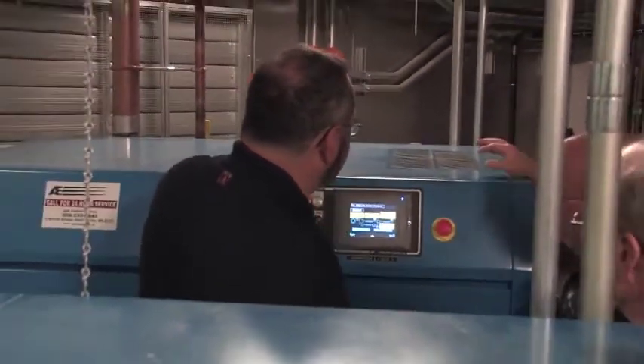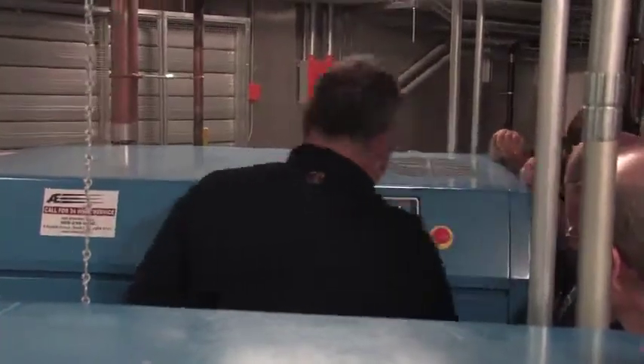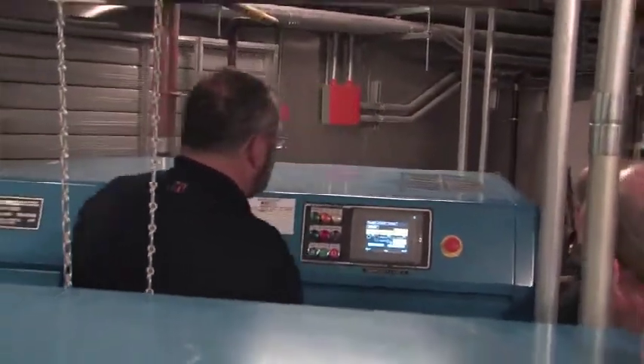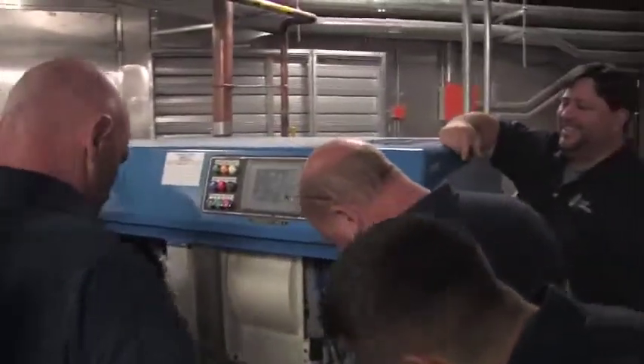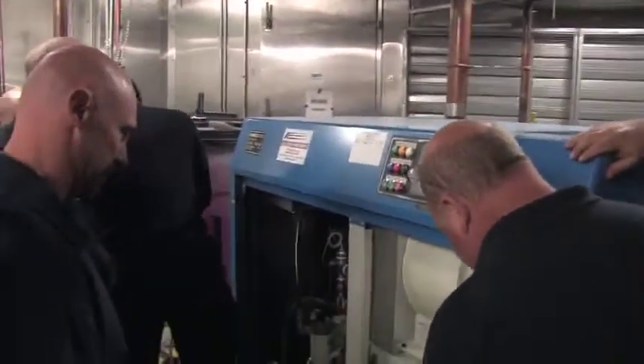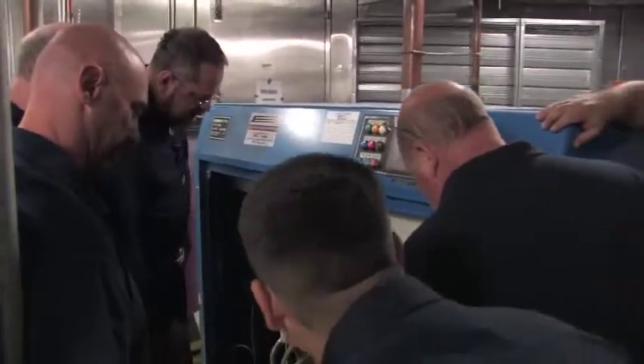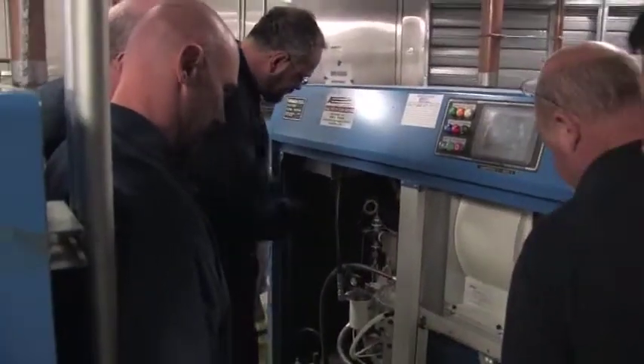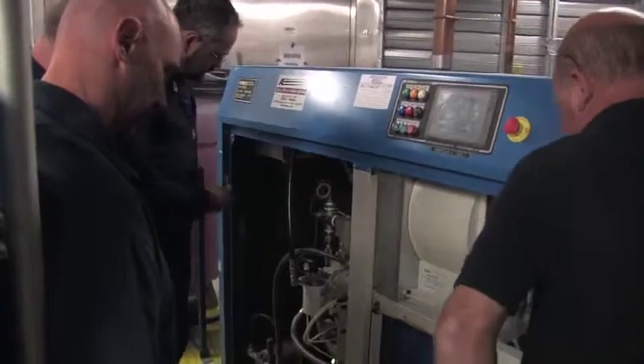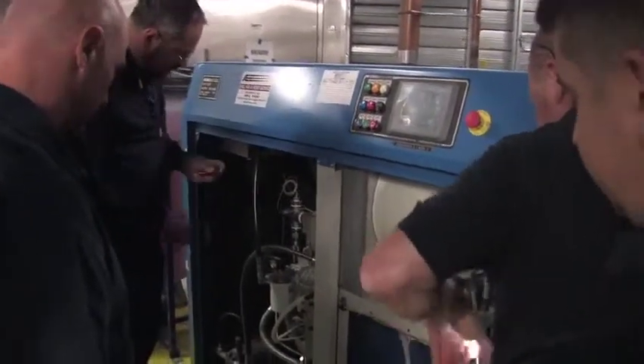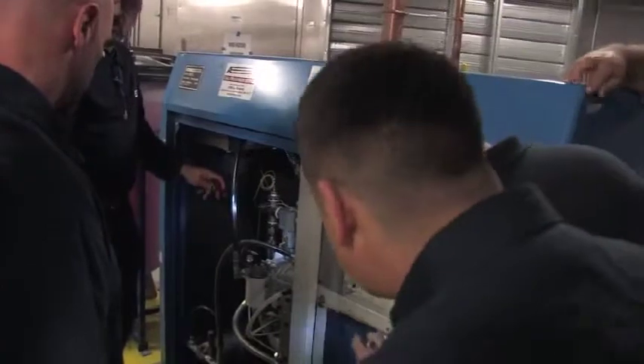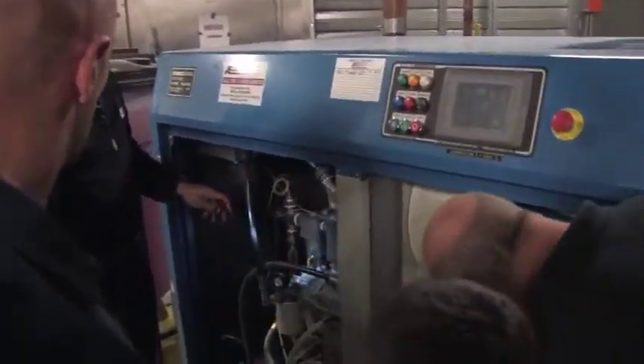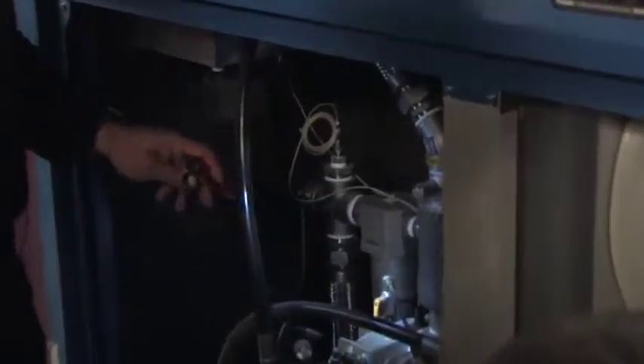Now right now we're in local. The reason I did that is we're going to kill the disconnect on this so we can open the cabinet. Now the nice thing about this one, compared to the others, is they still have the oil filter, the oil pressure fault test device. Bear in mind, anytime you work on it, you want that little valve to be open. This little valve here, you always want that open.